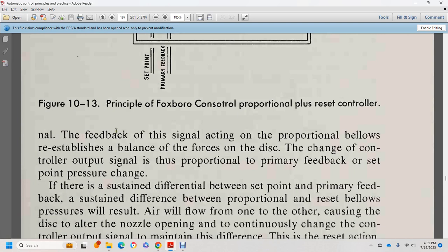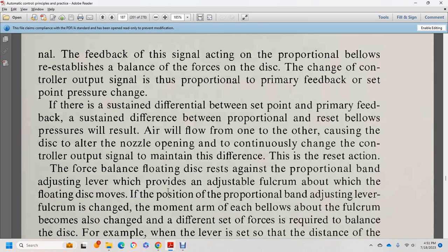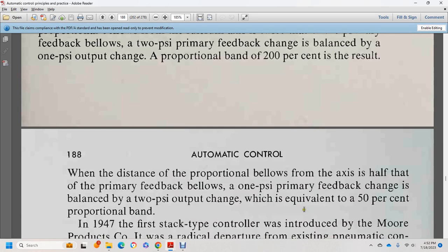Any change of pressure in the primary feedback or set point bellows slightly raises or lowers the corresponding side of the floating disc, changing the nozzle back pressure and operating the pilot valve to increase or decrease the controller output signal. The force balance reset action: a sustained pressure difference between proportional and reset bellows causes continuous change in the control output signal — this is the reset action. The proportional band adjustment lever provides the fulcrum. If the lever distance to the proportional bellows is twice that of the primary feedback bellows, a 2 psi primary feedback change is balanced by 1 psi output change — 200% proportional band. If the distance is half, a 1 psi change requires 2 psi output — 50% proportional band.